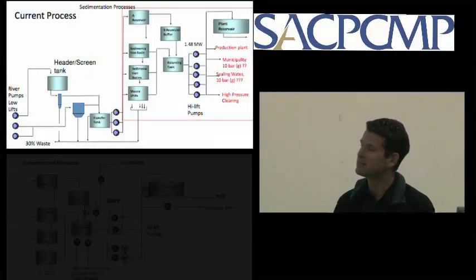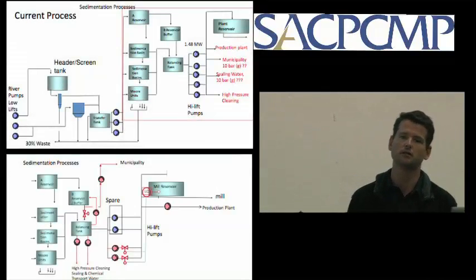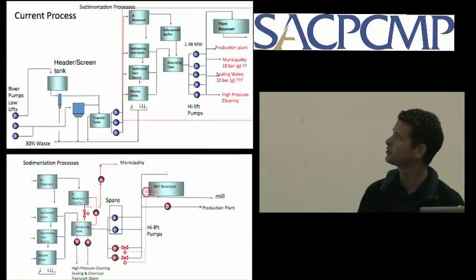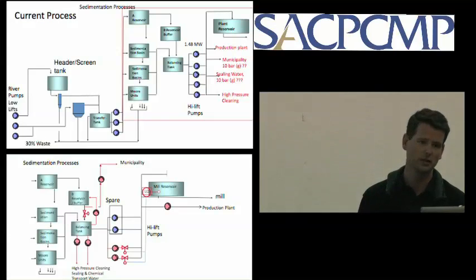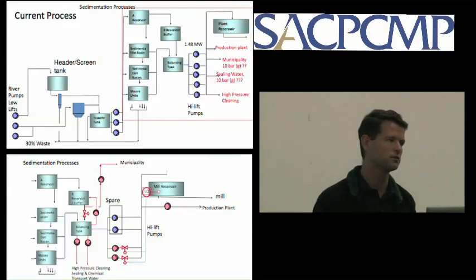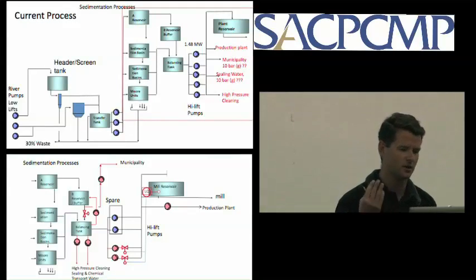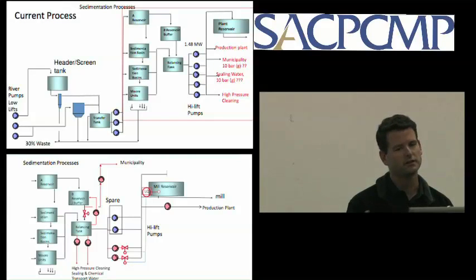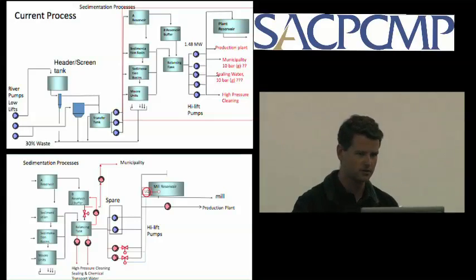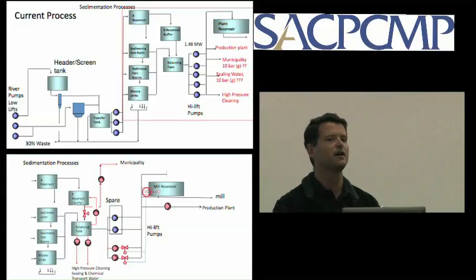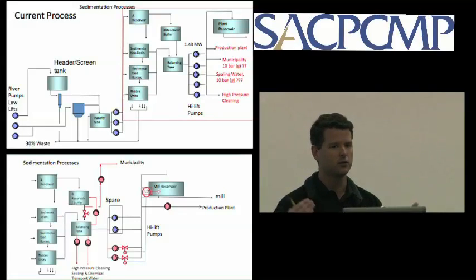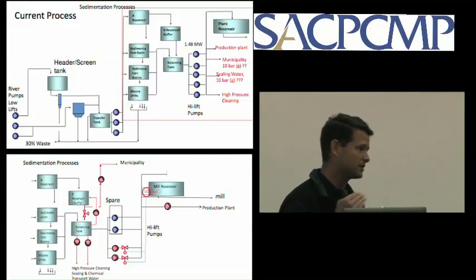First thing, we put in a telemetry system to transmit the mill reservoir level down to the control system. We actually completely upgraded their whole existing control system to put in a new SCADA system. One of the things they were scared of is that if you switch the plant off for 2 hours, then come back online and something goes wrong, as typically happens when you're starting up, you haven't got much reservoir level left to play with, and now you're waiting 2 hours to get an instrumentation guy out and everything.